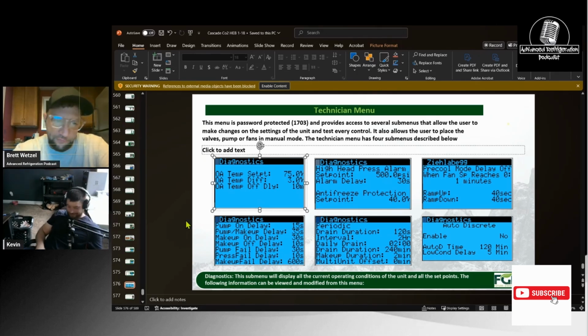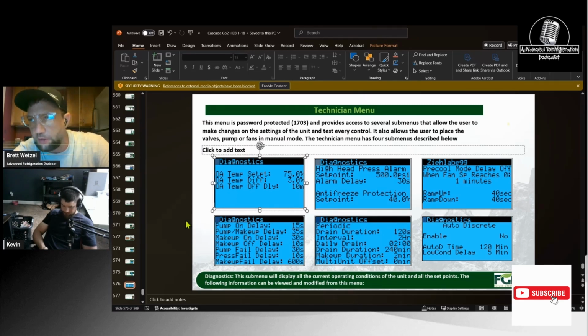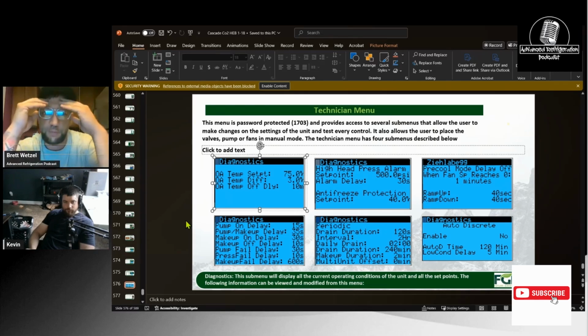Anyway, right here you have pump on delay, pump makeup delay, pump on delay. This is where you might increase it a little bit just to let that water fill a little bit above, right before it gets to the tippy top of the drain. Because when the pump comes on, it's going to drain a lot of that water, right? So instead of having it cycle that makeup water solenoid back and forth, you don't want to do that. We also have the pump fail delay, pump pressure fail delay, and makeup fail delay.